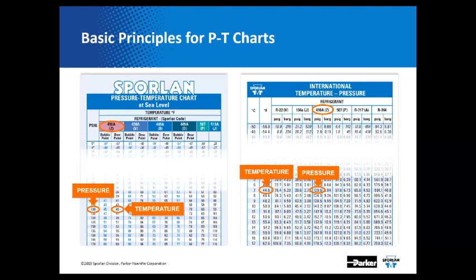You'll also notice that this PT chart has both a bubble point and a dew point. For 410A, which is fairly pure, it doesn't have significantly different bubble and dew points. But for a refrigerant like 448A, if you look two columns over — at 140 pounds — you would have a bubble point of 65°F and a dew point of 74°F. So if you're measuring superheat at the evaporator, you use 74 degrees; if you're calculating subcooling, you use 65 degrees. PT charts simply tell you the boiling and condensing points for refrigerants at specific pressures.